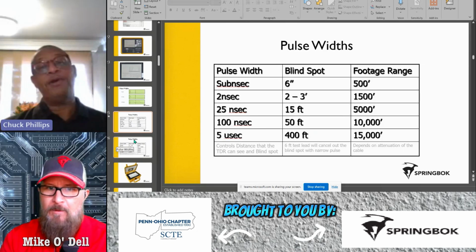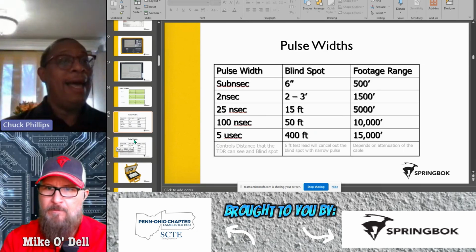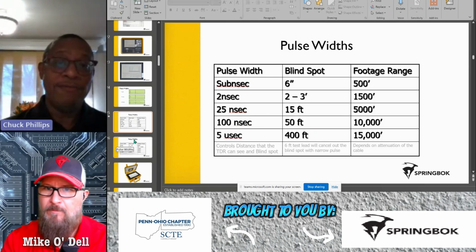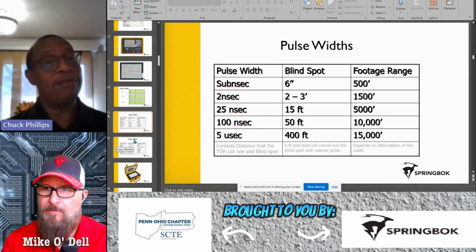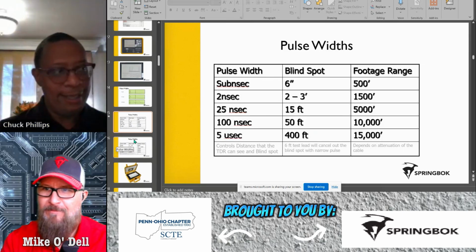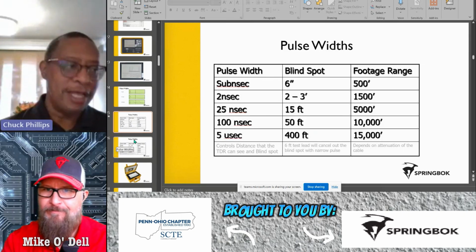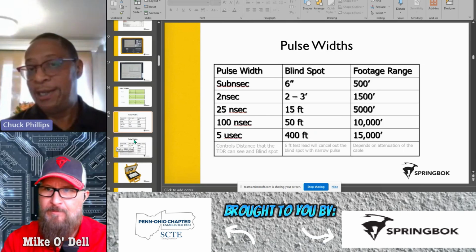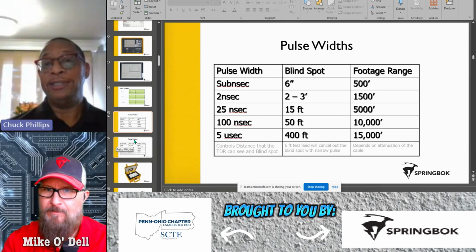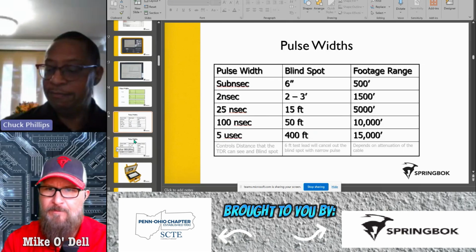And if I may add to that, if you have one of those high-end rolloffs where you suspect there could be water in the cable, I'm going to guarantee you that if you're looking at one of the more entry-level TDRs, I don't care whose brand it is, if you want to talk about hit and miss, it's going to be more miss than hit. That's why you're going to want the upper end TDR of whoever's TDR you're using to try and pinpoint where that problem is. This is good stuff.